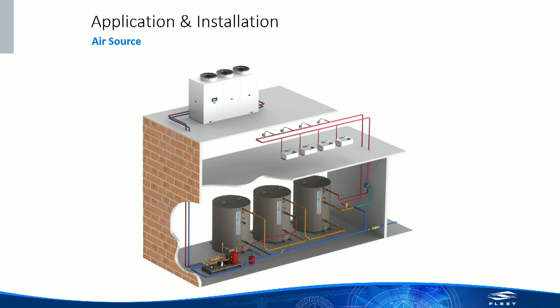Two, we are able to control flows. We talked about in the last one how we're doing pretty high lift, so we have high delta T's, low flow. We're able to segregate our flow rates from the actual domestic water usage within the building through this heat exchanger and control flow through the unit, which gives us better performance, better control, better reliability. And last and certainly not least, I think we all know heat pumps are very expensive pieces of equipment. So by going through a plate and frame heat exchanger, we actually protect the heat exchanger within the unit, the refrigerant to water heat exchanger, from the impurities and the dirt and everything else that we see in our domestic hot water streams.